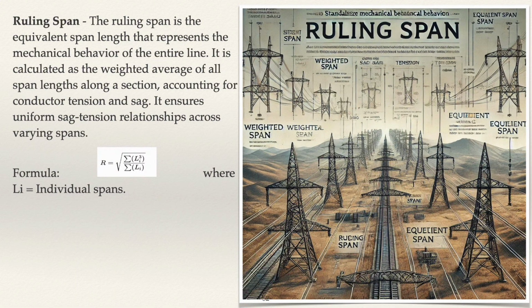Ruling span. The ruling span is the equivalent span length that represents the mechanical behavior of the entire line. It is calculated as the weighted average of all span lengths along a section, accounting for conductor tension and sag. It ensures uniform sag-tension relationships across varying spans. Formula, as mentioned, where L equals individual spans.